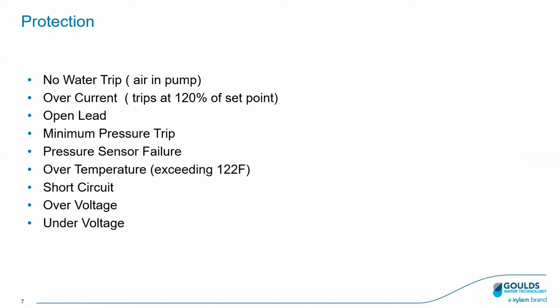Perhaps the most important benefit of the system is the multitude of protections that we are offering. No water protection for air in the pump. Overcurrent protection once it reaches 120% of current. Open lead protection, minimum pressure protection, pressure sensor failure, over temperature of the motor once it exceeds 122 F, short circuit protection, over and under voltage protection.